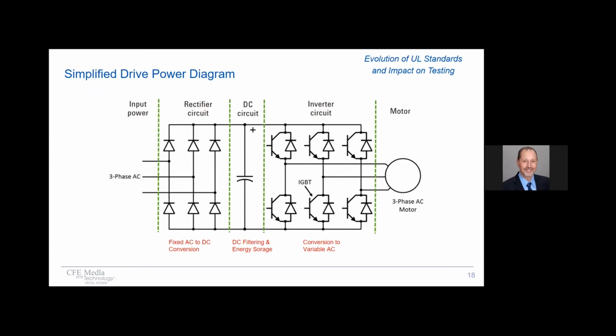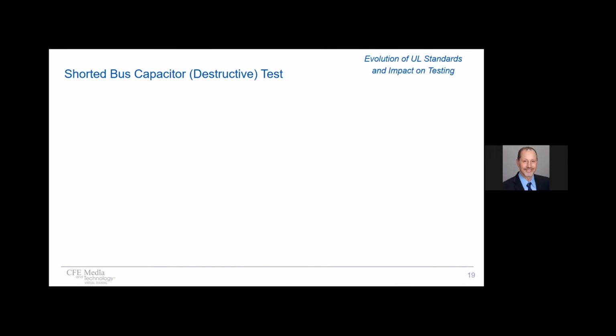Now, although the DC link often has inductance and multiple capacitors in series parallel combinations, before moving on, just remember that if something bad happens in the DC link or on the DC bus, there's potential for large amounts of energy to come from the power source straight through the rectifier. Let's keep that in mind. Now, remembering that basic diagram, let's discuss the component breakdown test just a little more. As we discussed before, UL now requires drive manufacturers to purposely create short circuits.